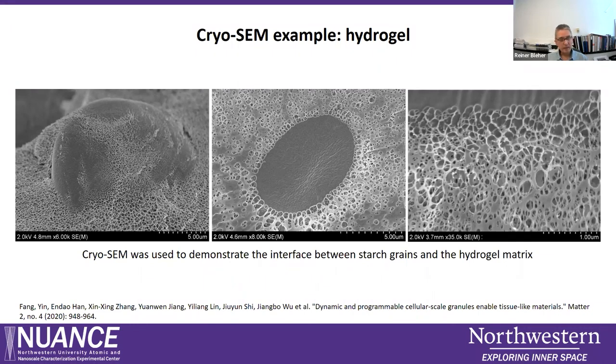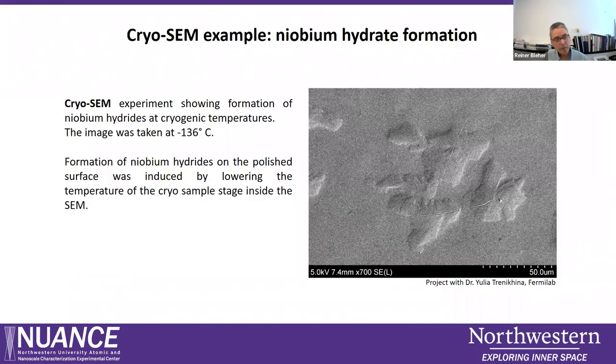One last example from the material science world: a polished niobium surface was cooled down in the SEM to minus 136°C, and during cooling we could observe the formation of niobium hydrides bulging out of the polished surface. This illustrates that the cryo stage can be used not just for frozen samples but also for cooling samples while observing them in the SEM, provided the samples can withstand the vacuum.